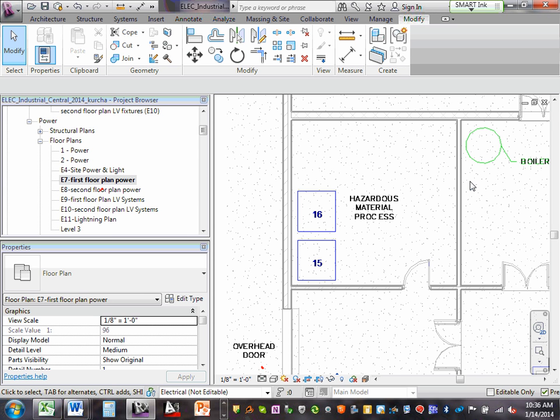What else was in the definition? I don't remember. But essentially, there are explosion-proof fire alarm devices available. What I would probably do is put an explosion-proof smoke detector in the room. I don't believe it's any greater than 30 foot by 30 foot, and again, the explosion-proof smoke detector is listed for 900 square foot coverage.